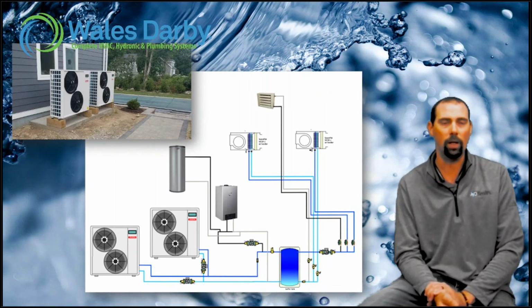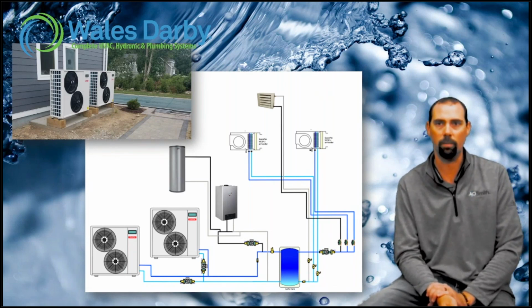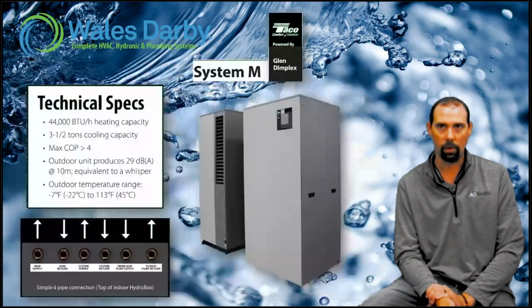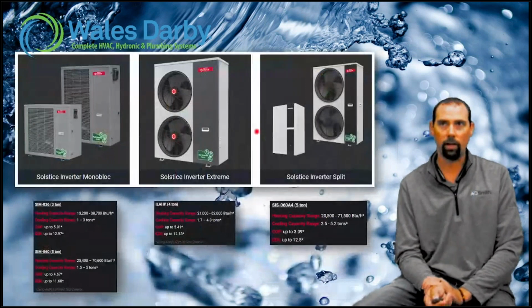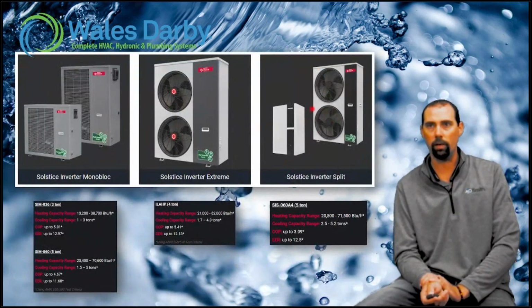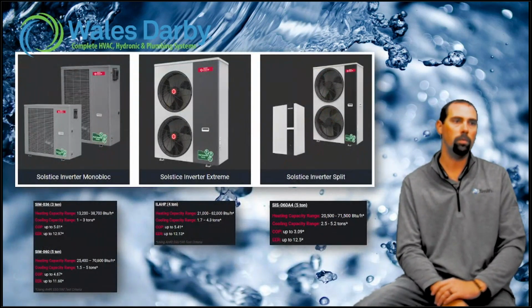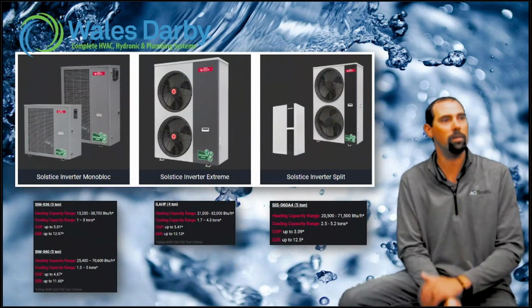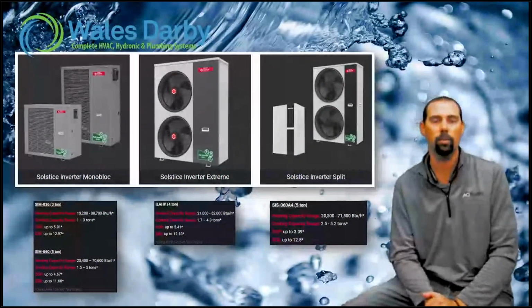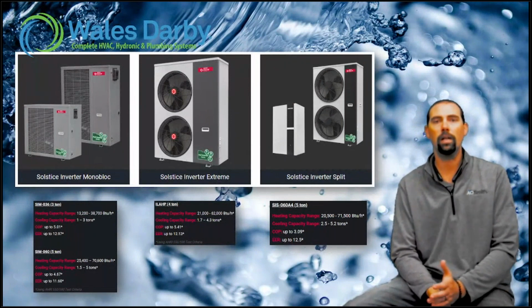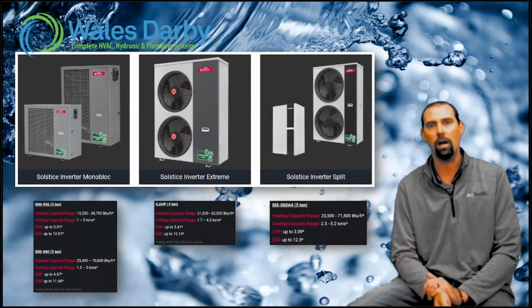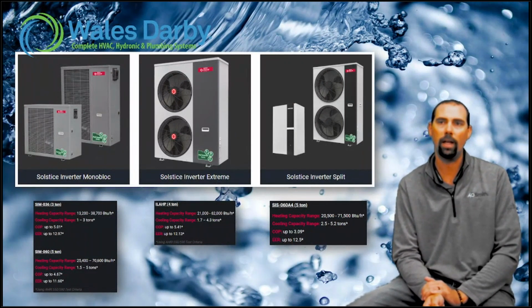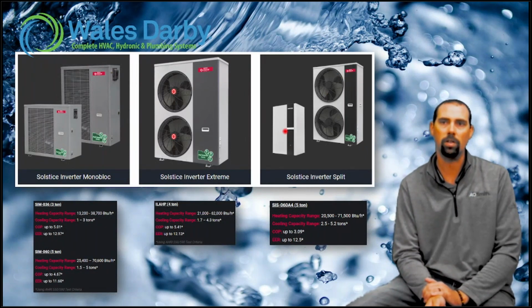I know initially when the split system came out, the split unit, we said great, we have no water outdoors, we don't have to put glycol in the system. But we do still need glycol in the system, just enough to keep it from freezing in the flat plate heat exchanger that's inside the box.